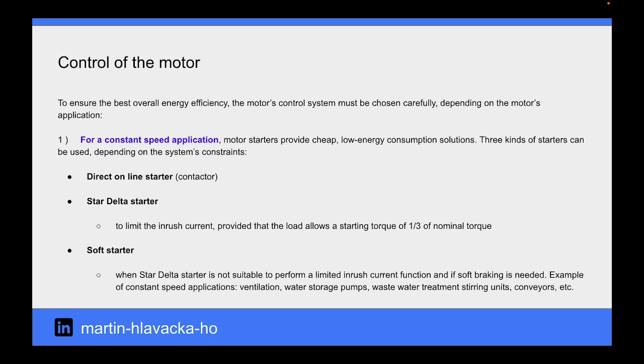Direct online starter; star delta starter to limit the inrush current, provided that the load allows a starting torque of one-third of nominal torque; and soft starter when star delta starter is not suitable to perform a limited inrush current function and if soft braking is needed. Examples of constant speed applications are ventilation, water storage pumps, wastewater treatment stirring units, conveyors, etc.